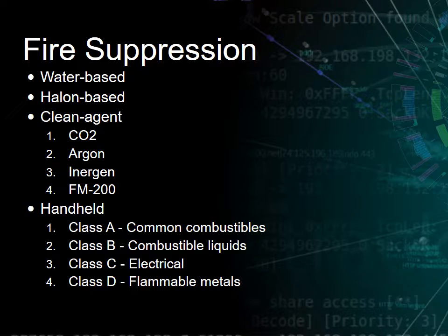So we put in an FM200 clean agent fire suppressant in one of our data centers. And so we met everything as far as the standard goes for fire suppression in a data center by putting that in there. But when the fire inspection came through, they failed us on the fire inspection in the data center.